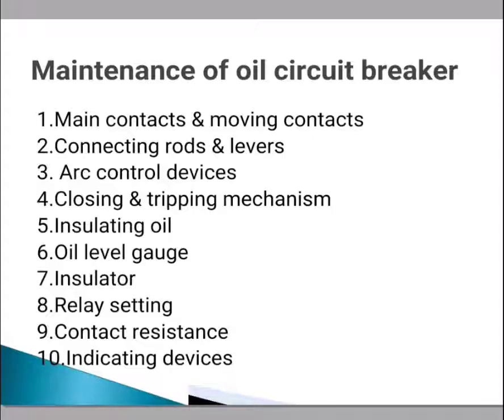For relay setting, check all relays for correct operation using a relay testing set — carried out half-yearly. For contact resistance, check and record the contact resistance — carried out yearly. For indicating devices, check indicators and lamps; replace or correct defective ones — carried out yearly.